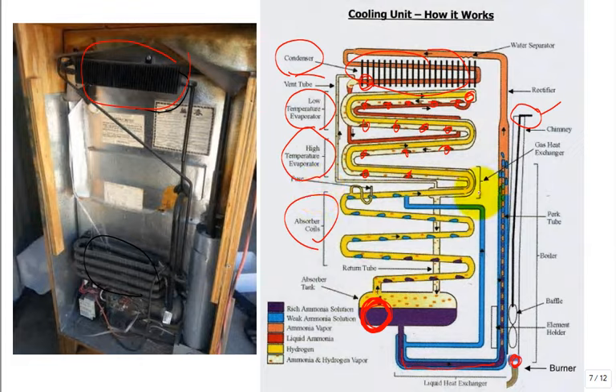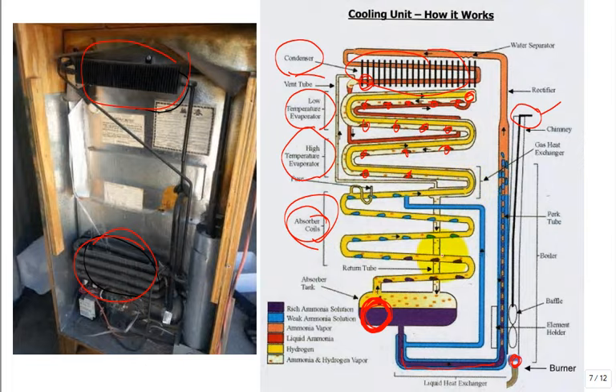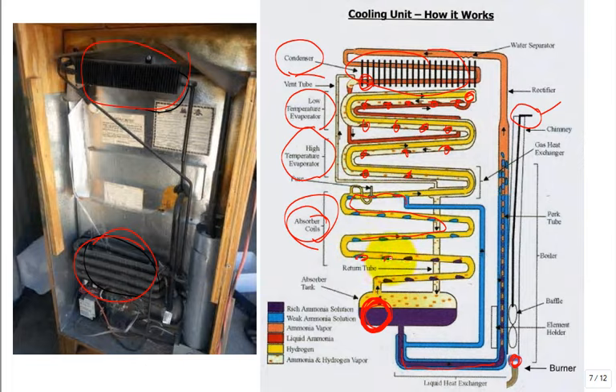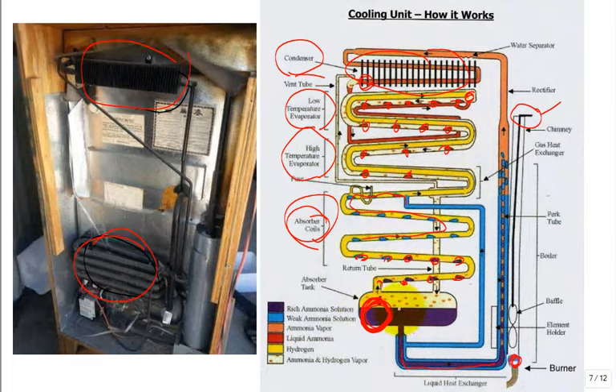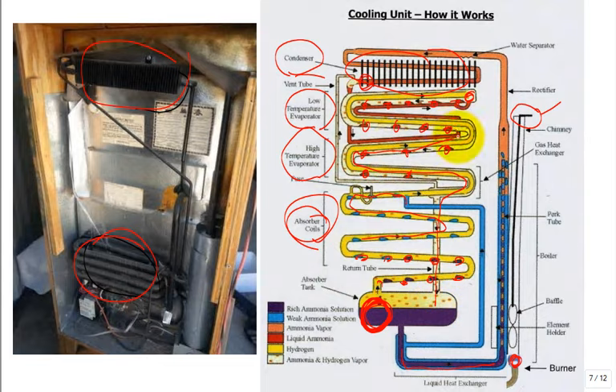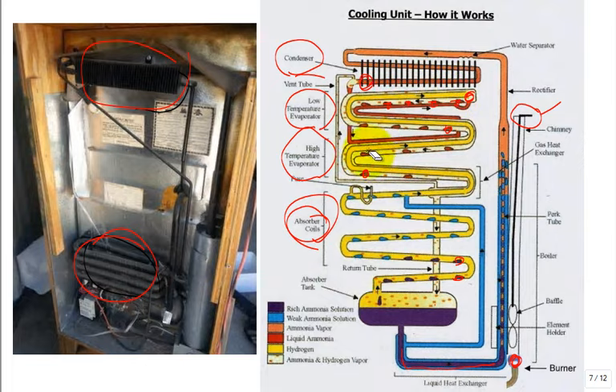You need to get it back to this absorber coil down in here. You have the weak solution going to come up to the top with the water, going to go dribbling down. Now you can see the droplets are getting more and they're getting darker, meaning it's picking up the ammonia that's flowing the other way. That collects the hydrogen, which is dumped down here. You try to get off the pure hydrogen. The hydrogen flows in the darker yellow inside the tube and then dumps here and flows back around.